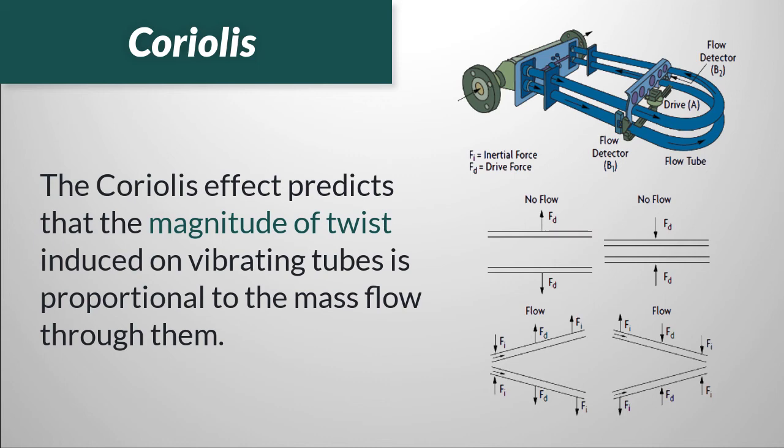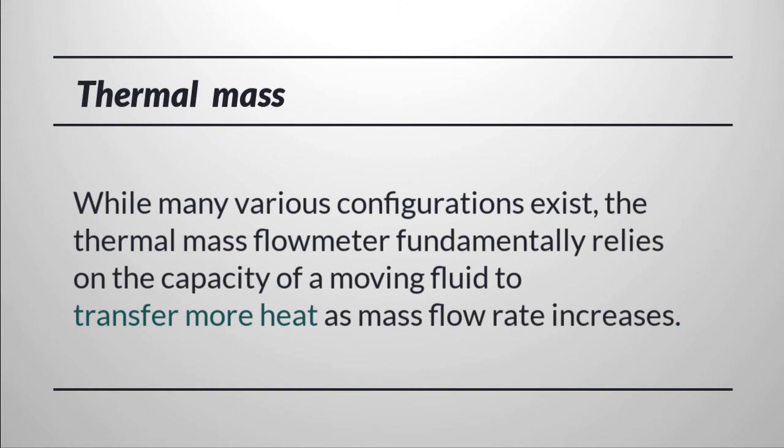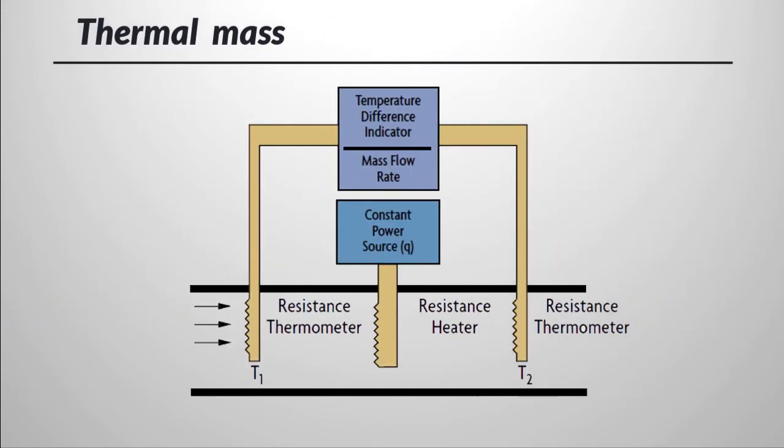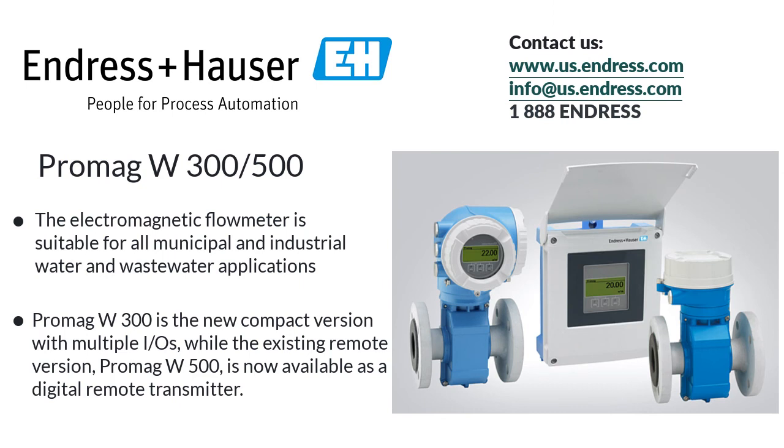Our final flow meter is the thermal mass flow meter, which measures the mass flow rate of gases and liquids by introducing a known amount of heat into the flowing stream and measuring an associated temperature change, or by maintaining a probe at a constant temperature and measuring the energy required to do so. They are often used for monitoring or controlling mass-related processes, such as the chemical reactions that depend on mass flows of ingredients. The Endress & Hauser ProMag electromagnetic flow meter is suitable for all municipal and industrial water and wastewater applications. The ProMag W300 is the most compact version with multiple IOs, while the existing remote version, ProMag W500, is now available as a digital remote transmitter.